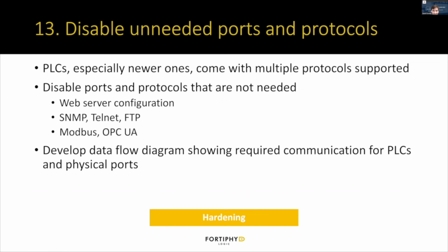Number 13 is disable unneeded ports and protocols. PLCs, especially the newer ones, come with a lot of different protocols supported. Thankfully for CODESYS, this is not exactly the case. OPC UA, I think, comes supported or enabled by default. Everything else you have to enable as you need. So the big idea here in general is disabling ports and protocols that are not needed, to reduce the number of options the attacker has to try to attack.